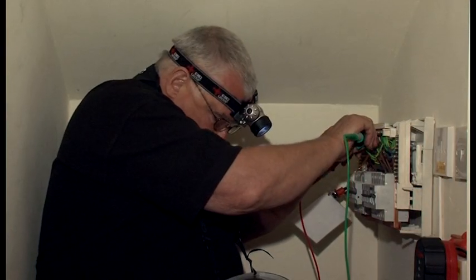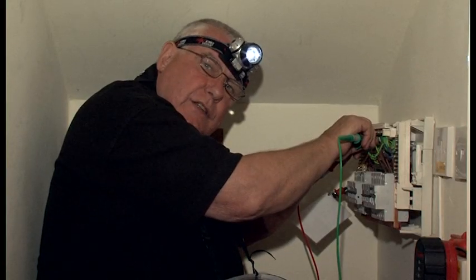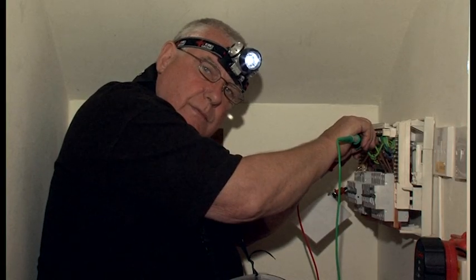Well, I've got a ring, that's for sure, and I've actually got 1.17 ohms, so that's perfect. Now I'm going to repeat this for all the other circuits. With initial verification, it would be necessary to carry out the crossover test on each ring, which includes going to socket outlets and taking additional readings. So why isn't this necessary for periodic inspection and testing, Tony?